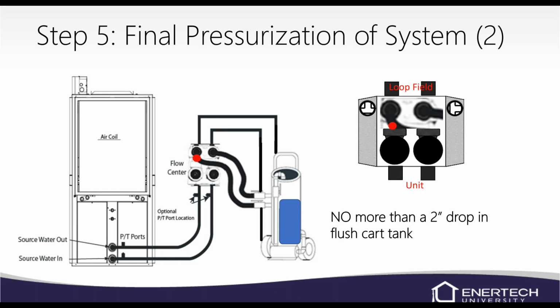But a good indication is a 2-inch drop when you deadhead the pump, because water does not compress. Air will, but water does not. So if there's air in it, when you deadhead the pump, it's going to push that air and drop the level in the cart. If you turn off the flush cart, that air can push back and overflow that cart. So those are two obvious indications of air in the system. Make sure we get all the air out, or you will burn up a pump.